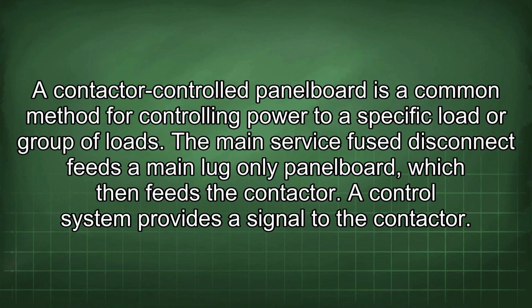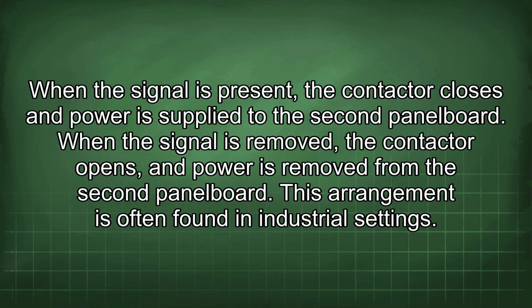Contactor-controlled panelboard is a common method for controlling power to a specific load or group of loads. The main service fuse disconnect feeds a main lug-only panelboard, which then feeds the contactor. A control system provides a signal to the contactor. When the signal is present, the contactor closes and power is supplied to the second panelboard. When the signal is removed, the contactor opens, and power is removed from the second panelboard.